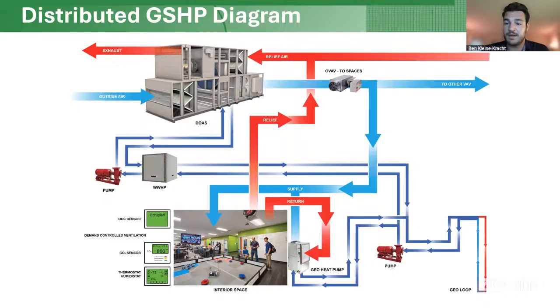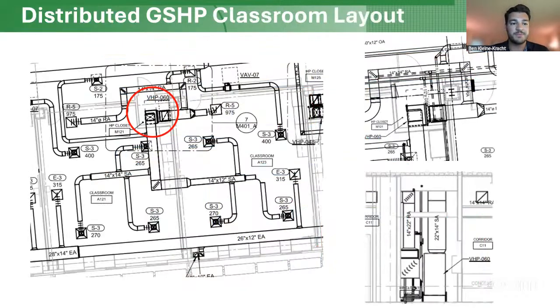These we would split. Here's a typical layout of a classroom here. This is one of the big cons that I was going to get to here, is that for the water source heat pump option, we have to play a bit of a hide and seek game, where we try to locate 6-foot by 4-foot closets to install these units right outside the classroom. And then it just dumps the air into the classroom, and we have a separate VAV from the DOAS, kind of shown there in the corners of the rooms. But really that closet is the crux.